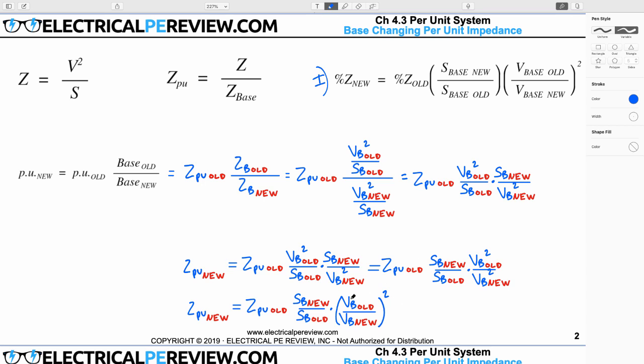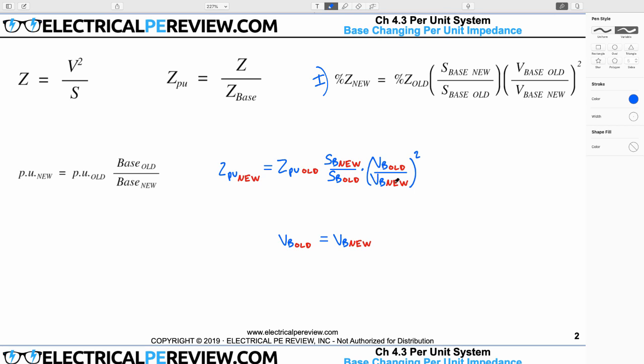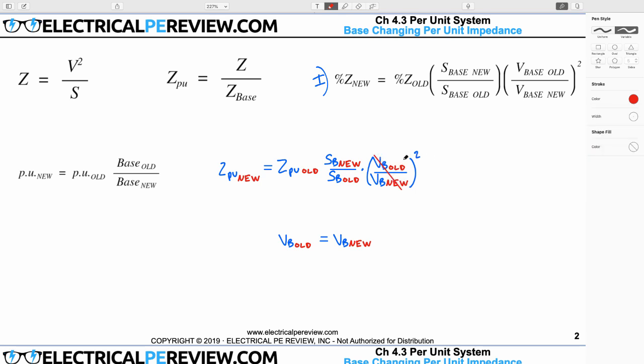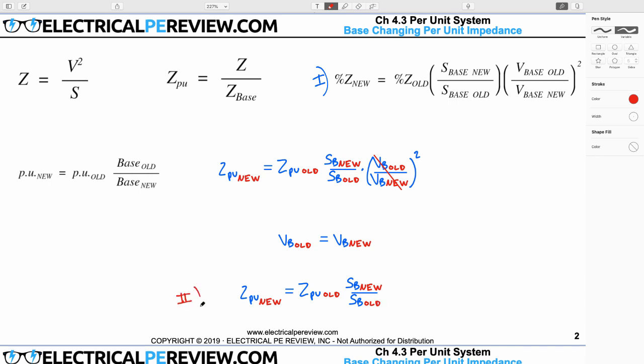Now, what happens when our old voltage base equals our new voltage base? If V_B_old equals V_B_new, this fraction with the squared term cancels — we're left with 1 squared, which equals 1. Multiplying by 1 makes no change. So when V_B_old equals V_B_new, we're left with a special condition: our new per unit impedance equals our old per unit impedance times our new power base divided by our old power base. That's formula two — the shortcut from the previous slide, now fully derived.